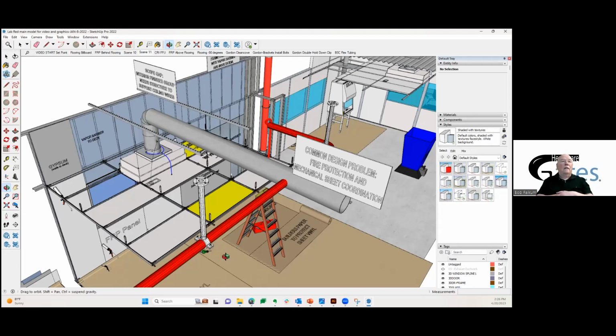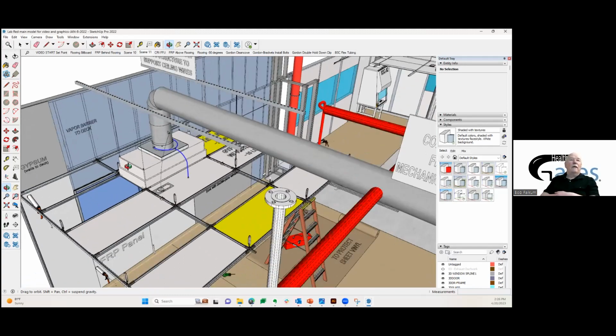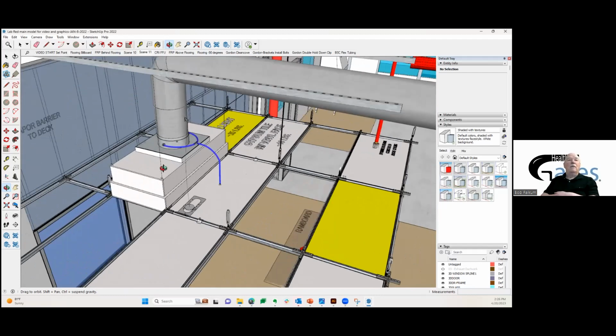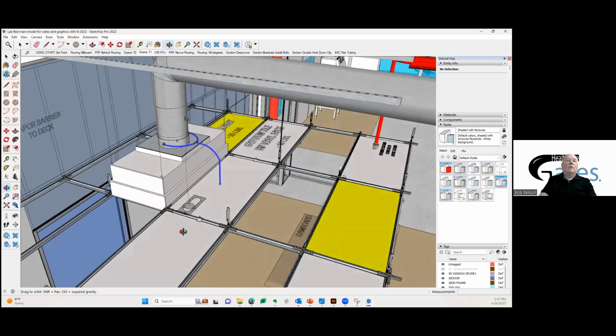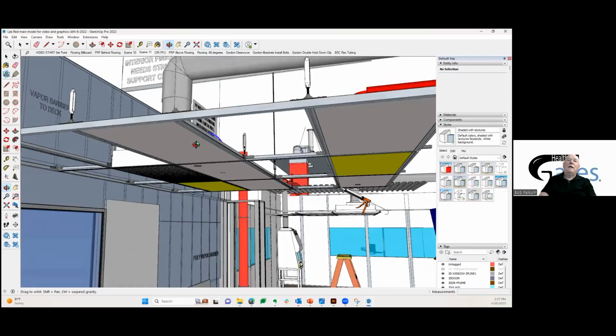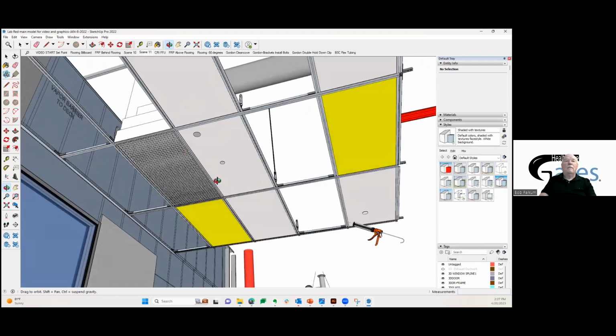You see the air coming in, going to what looks like a caboose — that's called a fan filter module. It's one way of introducing air into the clean room, probably the most common way. It's a HEPA filtered unit, 99.99% pure at a certain size micron. There's a motorized control that allows you to ramp it up or down, giving an adjustable variable speed. That control, which just looks like a fan speed switch, should not be on the machine the way it comes — it should be remote.